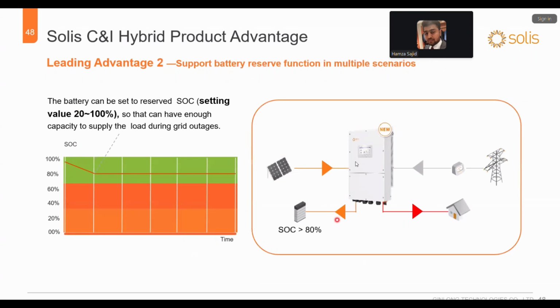Now, we also have the battery reserve function. In multiple scenarios, you need the battery reserve function. The battery can be set to a reserve SOC value from 20 to 100%, so that it has enough capacity to support the load during a grid outage.